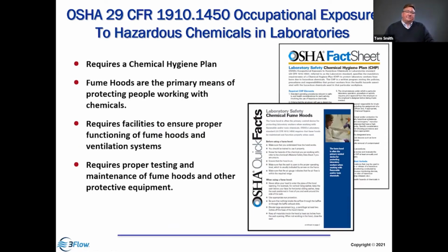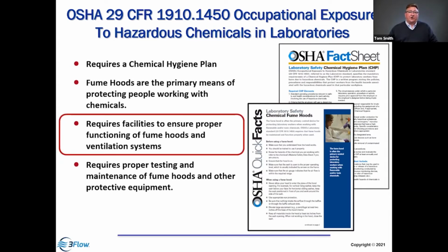So OSHA comes in. 1910.1450, the lab standard, says that it requires all facilities to ensure the proper functioning of fume hoods, and it requires proper testing and maintenance of fume hood systems. That's the law, right? So if you're governed by OSHA rules and regulations and have to comply with OSHA, it says that you must ensure the proper functioning of fume hoods. You must have validation that they're working properly and capable of protecting the occupants. And that's the only reason it was installed. So that's what we're going to do today and tomorrow, is talk about how we achieve that objective.